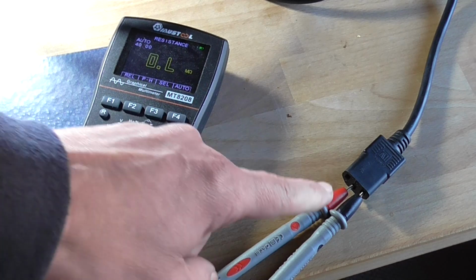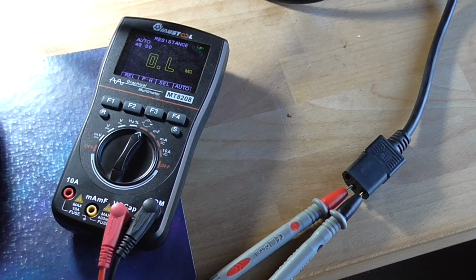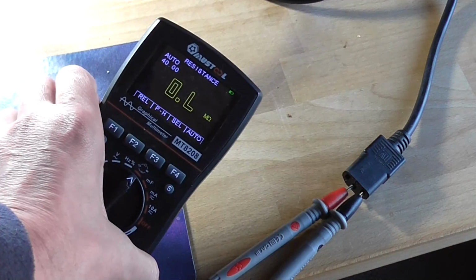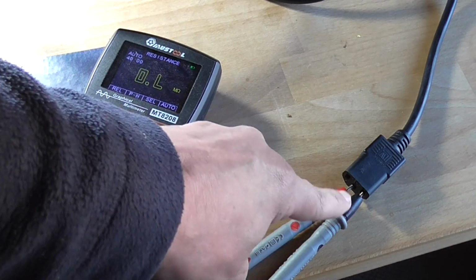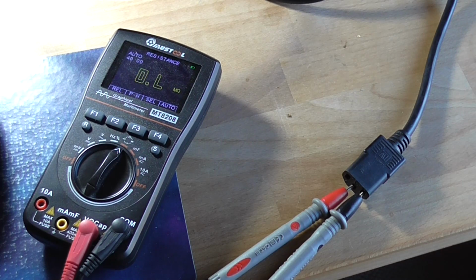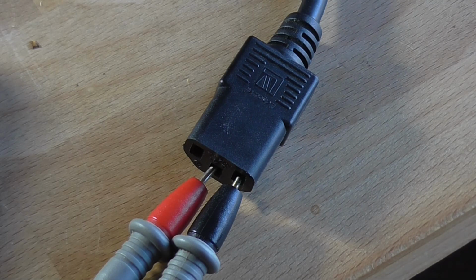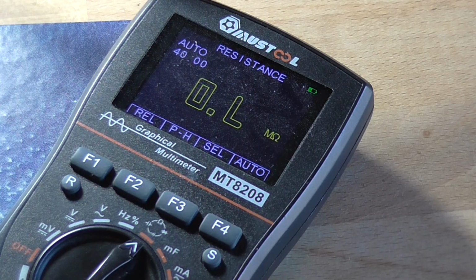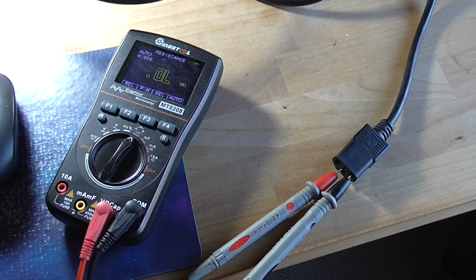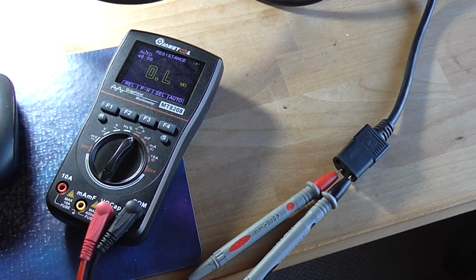So to demonstrate that the neutral and the earth pins of a power point or power outlet are directly connected together electrically, I'm going to measure with a multimeter the resistance across the earth and the neutral. Now, it is plugged into a power board, but the power switch on the power board is off. And the power switch on the power board switches both active and neutral. Now, I will stress, do not try this at home unless you know exactly what you're doing. Do not go sticking random things into power outlets or power cords, such as multimeter probes, because if you get it wrong, well, you run the risk of causing damage to things, such as the multimeter. Now, I will turn the switch on and we'll watch the meter.